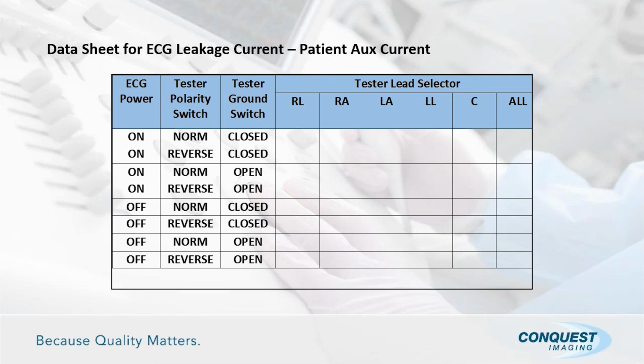Then we're talking the next three, or the patient lead leakage, and the next one, which is your patient auxiliary current, as well as your MAP. They're all the same tests that you have to run. So as you're in the on, normal, closed position, you should go to each one of those settings on your analyzer and just record the readings while you're there, as opposed to doing all of one and then having to start all over and do it again. Do them simultaneously. That way you're not turning the system on and off. So those are your 3 data sheets right there that are required for the conditions that you're testing.